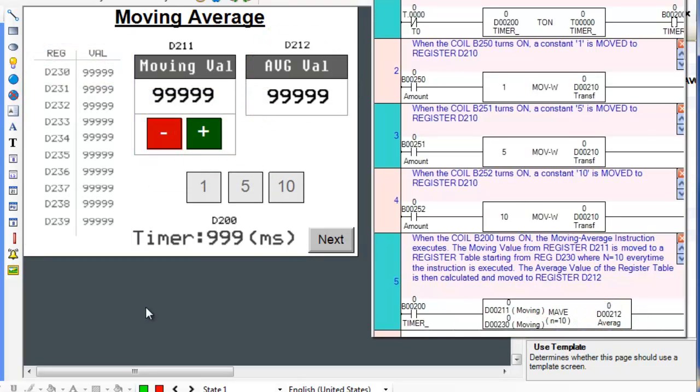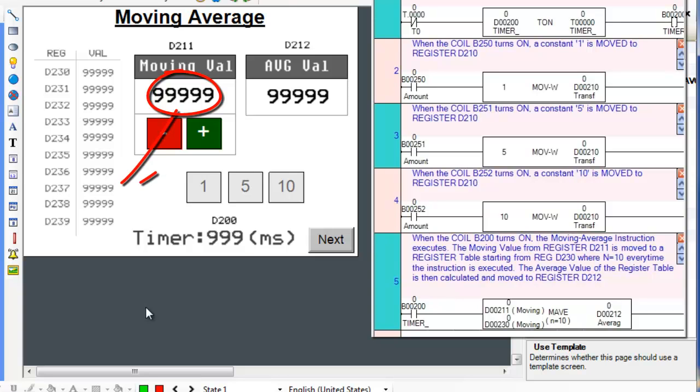When the Moving Average ladder instruction is executed, the value in Operand A is moved to a particular register in the register table. When the instruction is executed again, the value in Operand A, whatever it is because it can be changed, is moved to the next register in the register table. And it will continue to add Operand A's value in the register table as long as the instruction is executed.